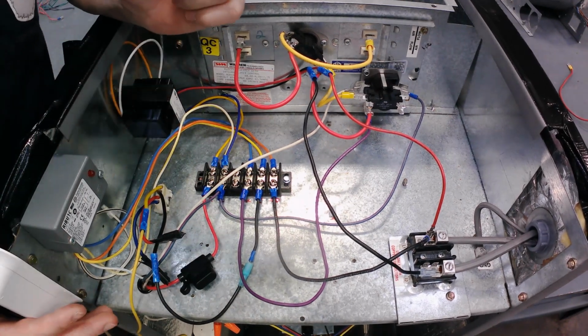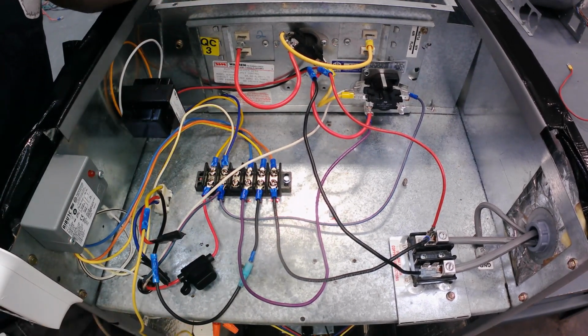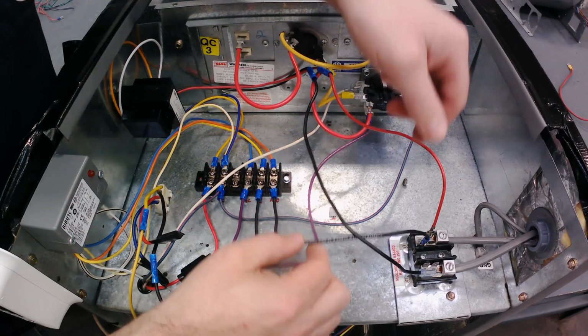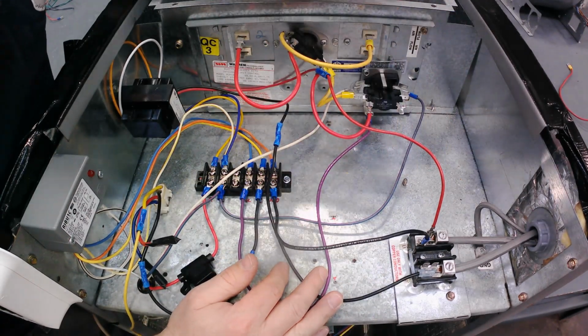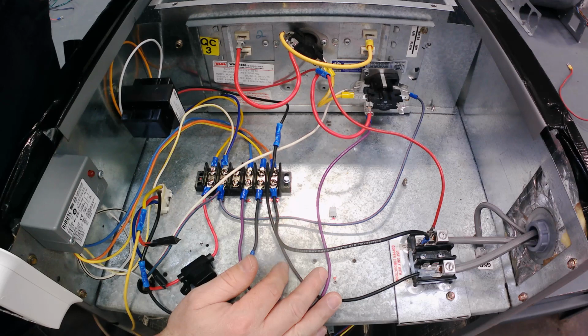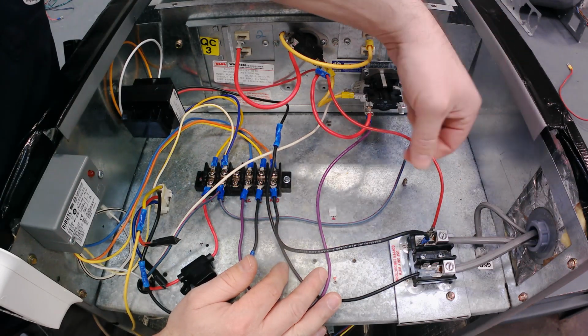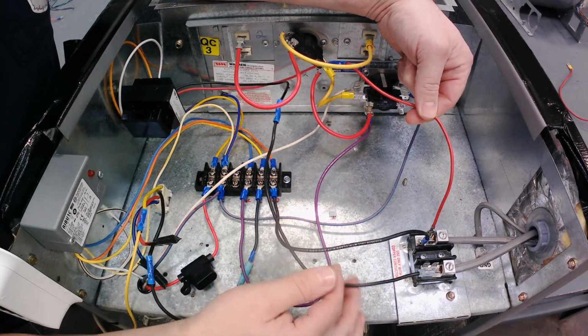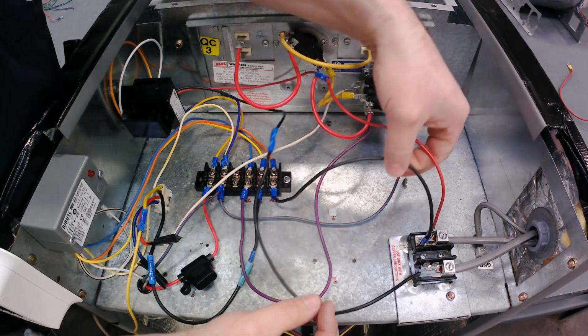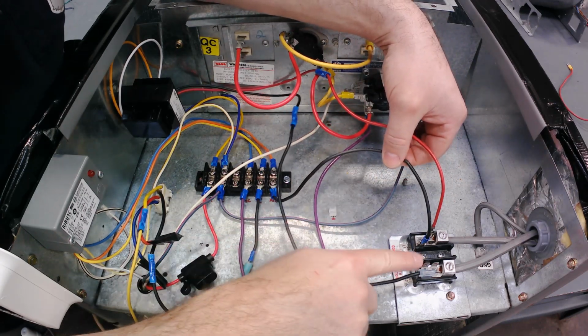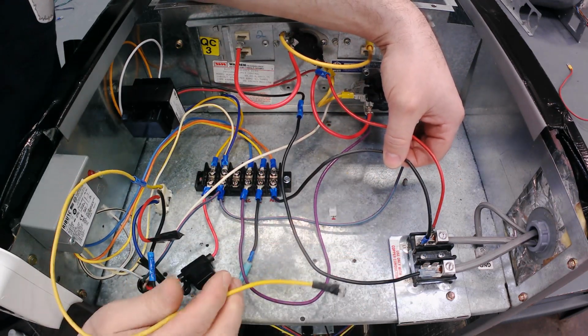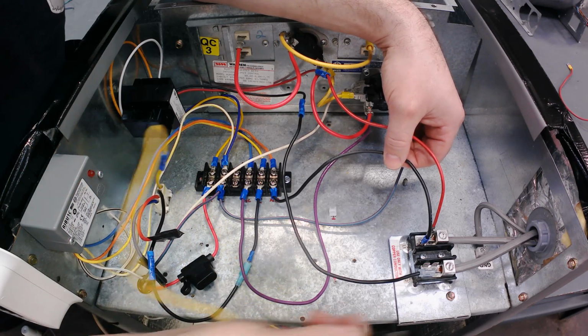We've got our thermostat wired, we've got the low voltage connections here. The only thing that I didn't do, and if you look at it here, we haven't added the high voltage for the heat strip. We'll do that in just a second. But I've got power coming out to my transformer, and I've got power coming back. I've got power going into my fan, and I don't have another terminal there. We have to terminate the L2 side of the fan motor.